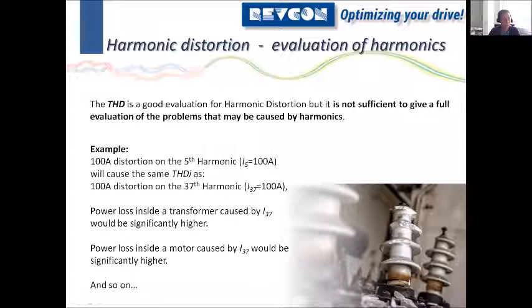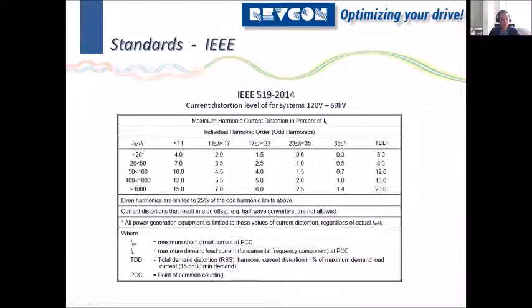Some people say that a transformer doesn't transmit the harmonics to the next level. That's only partly true, because a transformer can transmit harmonics, and the 5th, 7th, 11th and 13th you will see on the medium voltage side. There will be less, but they are not removed, and a part of them is turned into heat. So transformers are not the solution to solve harmonics. Okay, I hope that was clear. And that is basically the background of why you should keep a good eye on high harmonics.